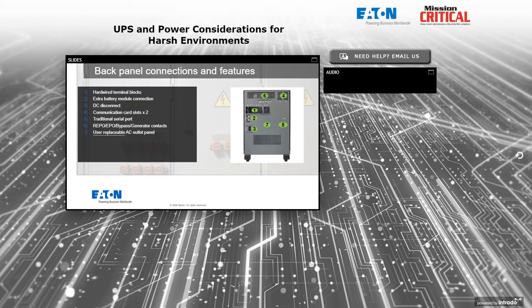So it needs to be a quick disconnect usually, but also needs to be safe, whether the external battery is connected or disconnected, regardless of the status and operation of the UPS. A DC disconnect itself or a circuit breaker for that external battery should be available on the UPS externally, so the operator can disconnect the battery at any time.